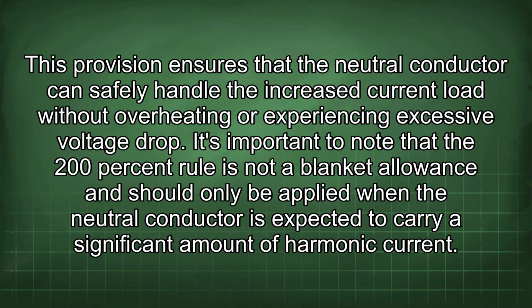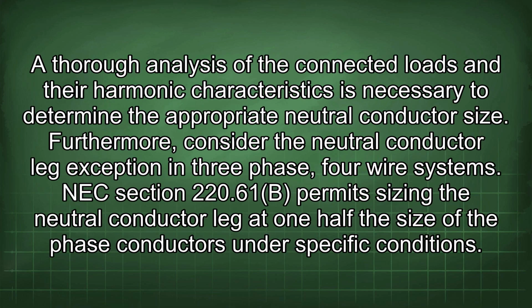It's important to note that the 200% rule is not a blanket allowance and should only be applied when the neutral conductor is expected to carry a significant amount of harmonic current. A thorough analysis of the connected loads and their harmonic characteristics is necessary to determine the appropriate neutral conductor size. Furthermore, consider the neutral conductor leg exception in 3-phase, 4-wire systems. NEC section 220.61(B) permits sizing the neutral conductor leg at 1/2 the size of the phase conductors under specific conditions.